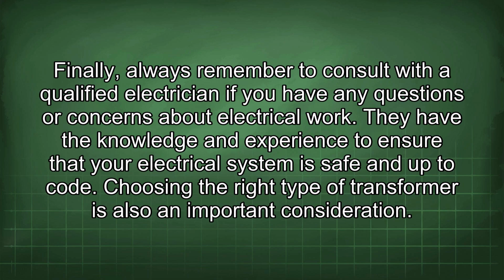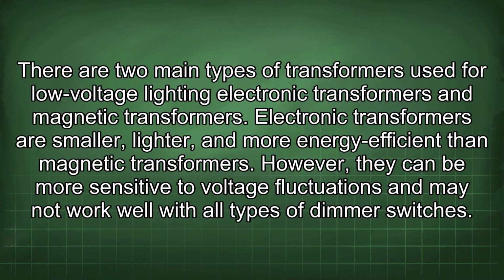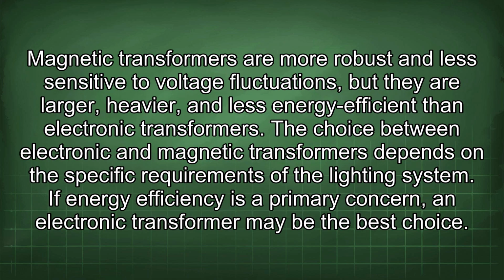Choosing the right type of transformer is also an important consideration. There are two main types of transformers used for low-voltage lighting: electronic transformers and magnetic transformers. Electronic transformers are smaller, lighter, and more energy efficient than magnetic transformers. However, they can be more sensitive to voltage fluctuations and may not work well with all types of dimmer switches. Magnetic transformers are more robust and less sensitive to voltage fluctuations, but they are larger, heavier, and less energy efficient than electronic transformers. The choice between electronic and magnetic transformers depends on the specific requirements of the lighting system.